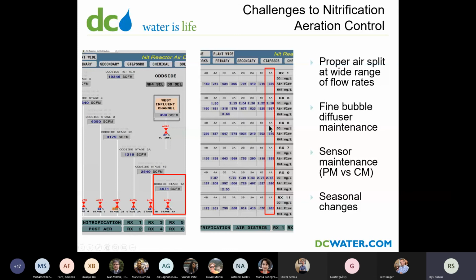So somebody has to go out there and manually set the butterfly valve to be able to get a good split. But the problem is, as this control air valve goes up and down to meet various airflow set points, it's always hard to get a good air split on the full wide range. So even if the controller is working really well on the particular reactor that we're using to set the airflow, there could still be ammonia breakthrough on the other reactors just because of that flow split.